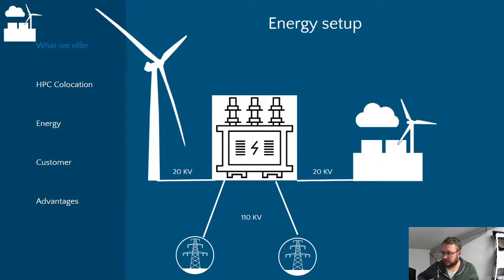How's the actual energy setting set up? As I said, this is our wind turbine. It produces energy at the 20 kilovolt level, and nearly 90 turbines feed this into the central switchyard you saw earlier. The switchyard has 4 big transformers in a redundant setup so they can be switched over, and the energy is transformed to the 110 kilovolt level, then fed into 2 separate directions, into redundant switchyards, into the electric grid, where it's transported and used, hopefully in Hamburg and beyond, which is a big issue.